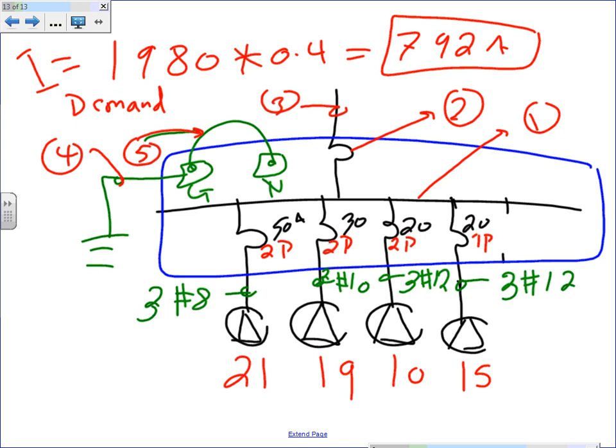Straightforward, right? So you have to supply the neutral only if it's needed. If it's 2 pole, 50, I don't need a neutral. It's two conductors for the 2 hots, and the third one is for the equipment ground conductor. Makes sense? Here, it's single pole, but why do I have 2 conductors? 1 hot, 1 neutral, and why do I need a third one? Ground, equipment ground conductor.